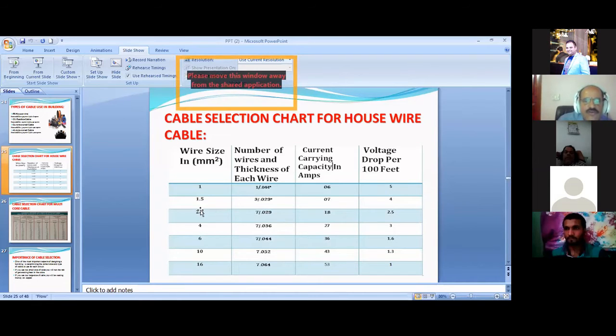See, if you see 2.5 square mm, it draws 18 amps. Whereas when the voltage drop is there, it is less. That means it draws only 15.5 amps. So when you are using a 15 amps circuit plug with 2.5 square mm, you should be sure that there are no voltage fluctuations.